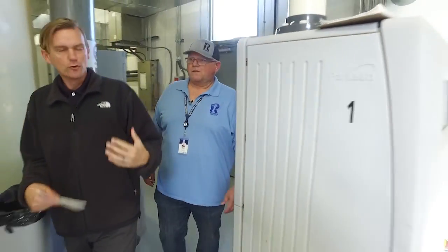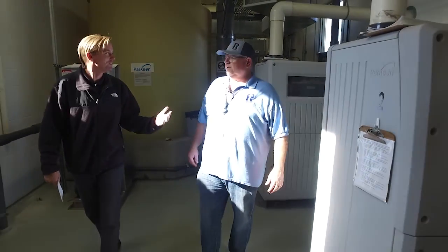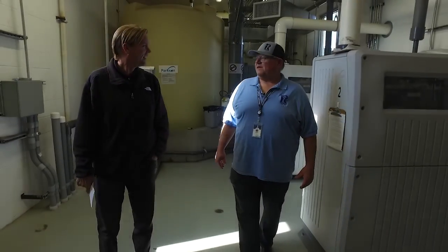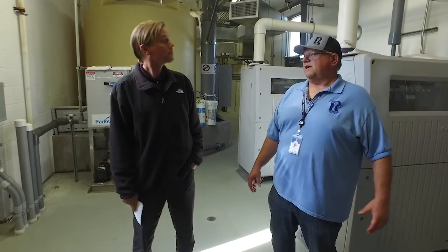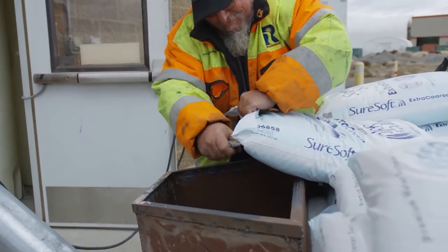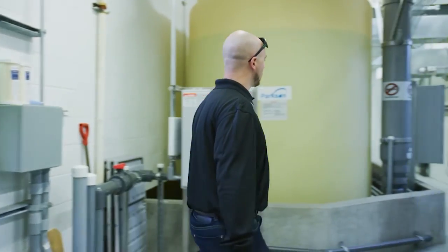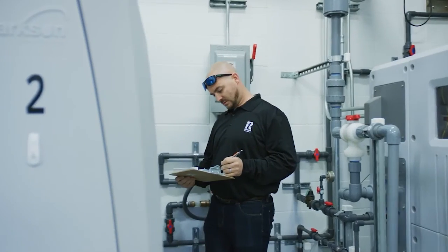But talk about some of the improvements, upgrades, maybe changes to how we treat water here at the City of Richland that have happened over those 56 years. Yeah, and so back in 1995, we did a full plant upgrade, and we added 4 more filters up to the top and changed some of our chemical processes. And then in 2016, what you see here is we changed our disinfection. We went from gaseous chlorine, which is a very unstable product, to on-site generation. And on-site generation, we take bulk salt in, we add water, soft water to it, and produce a brine solution. And that brine solution goes through these generators, which has electrical plates in them.